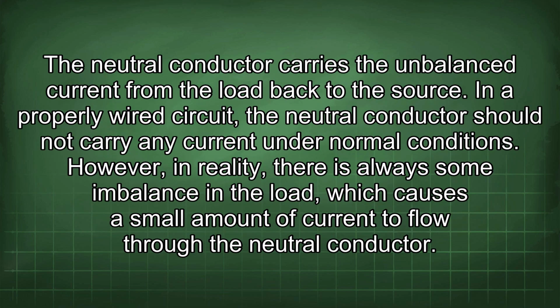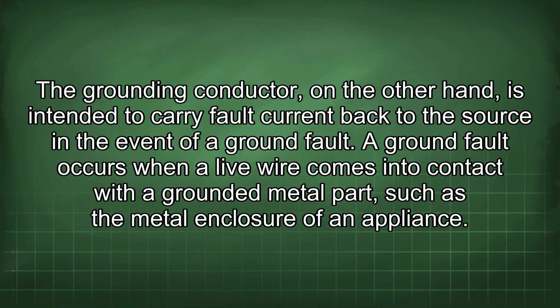The neutral conductor carries the unbalanced current from the load back to the source. In a properly wired circuit, the neutral conductor should not carry any current under normal conditions. However, in reality, there is always some imbalance in the load, which causes a small amount of current to flow through the neutral conductor. The grounding conductor, on the other hand, is intended to carry fault current back to the source in the event of a ground fault.